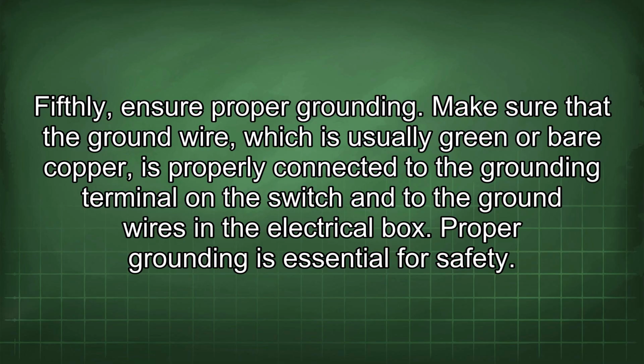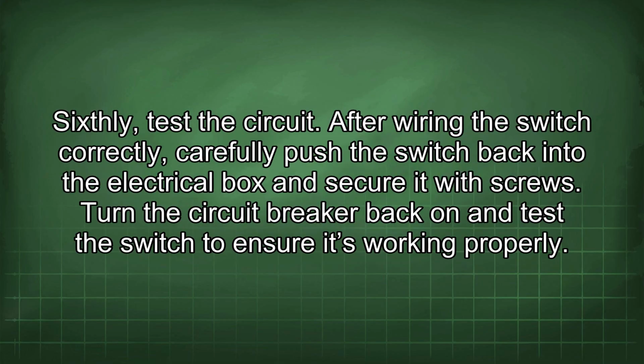Make sure that the ground wire, which is usually green or bare copper, is properly connected to the grounding terminal on the switch and to the ground wires in the electrical box. Proper grounding is essential for safety. Sixthly, test the circuit.